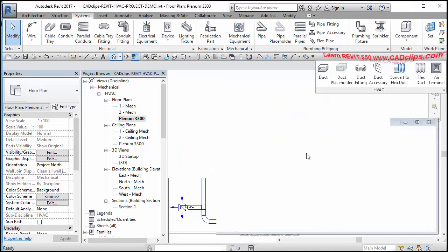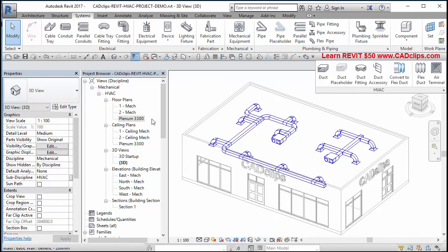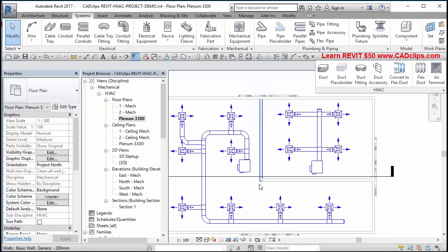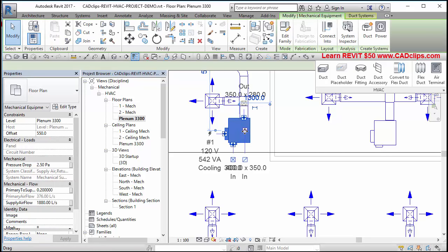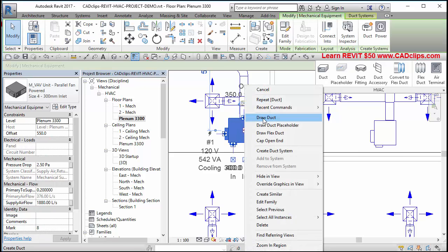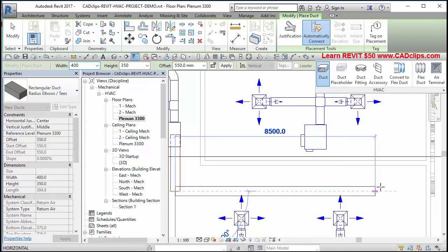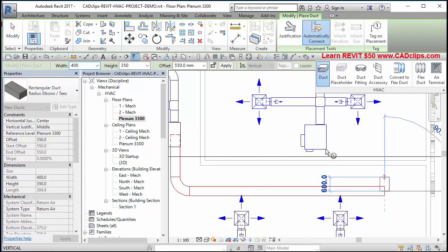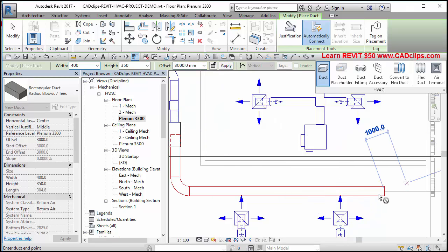All right, let's have a look at our 3D view. Pretty good. Back to our plenum. And now for our return, all we're going to do is click on here, right click on this return connector, and say draw duct. I'm going to draw that duct along here. Over to here, and then maybe it's going up to the roof or something.